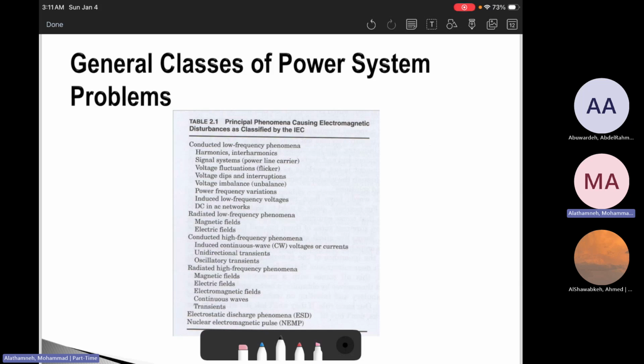Every power quality problem can be classified by asking two questions. Is this steady state or non-steady state? Or I would say, is this permanent or temporary? If it is steady state or permanent, it is continuous distortion, continuous imbalance, continuous frequency deviation. If it is non-steady state, it is something transient or temporary, events like sag, swell, transient interruption. The other thing we need to make sure of is where it originates. Is it from the utility side, from the customer side, or from the interaction between the customer and the utility? These classifications are the beginning of troubleshooting.